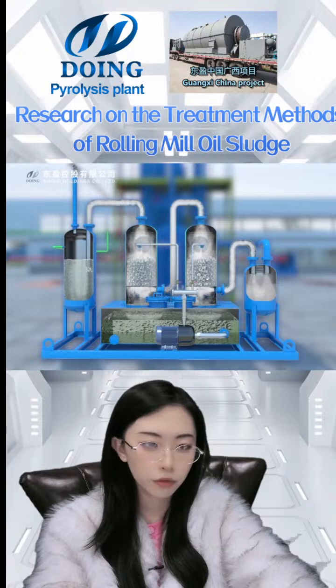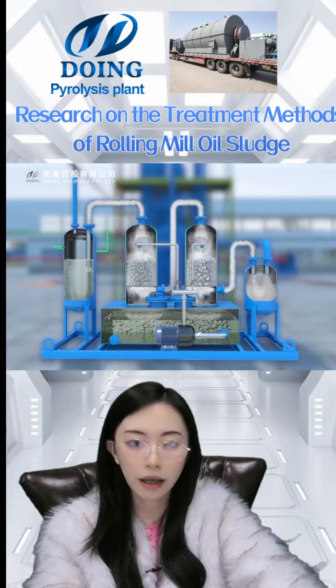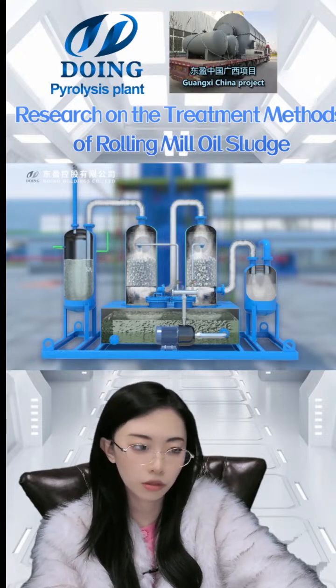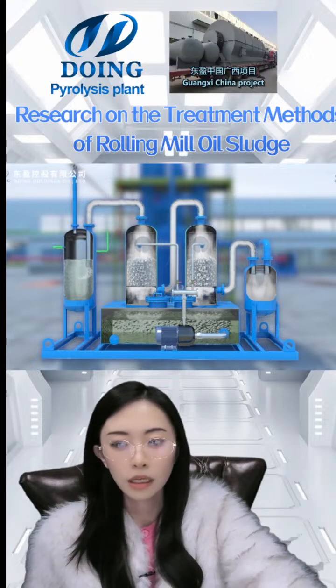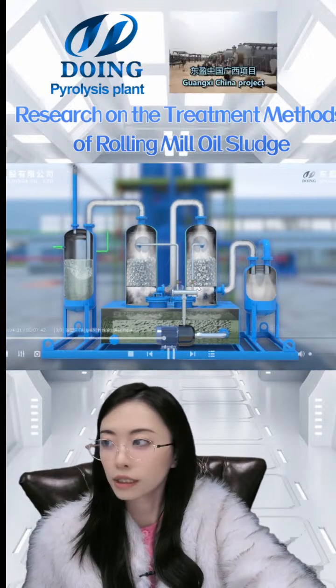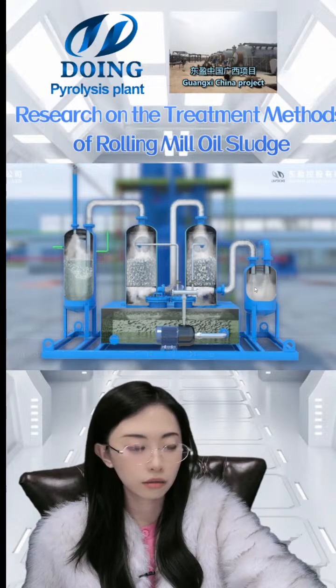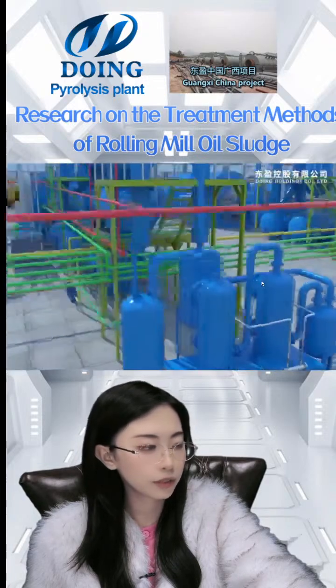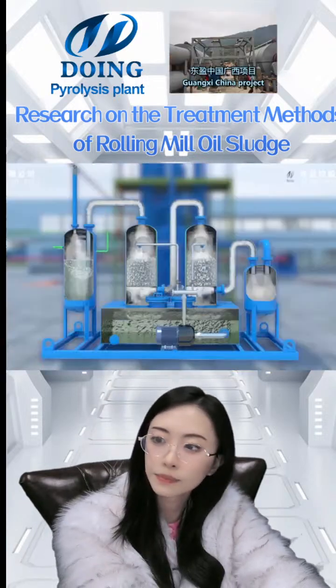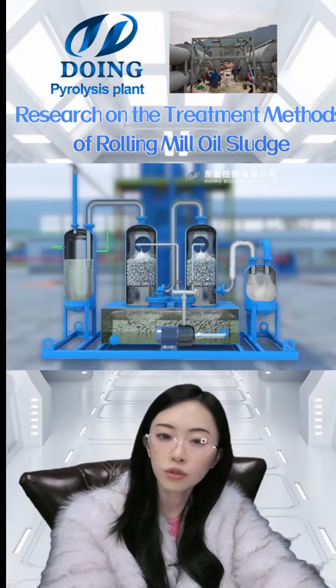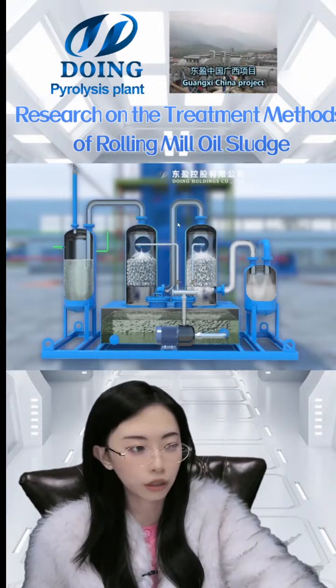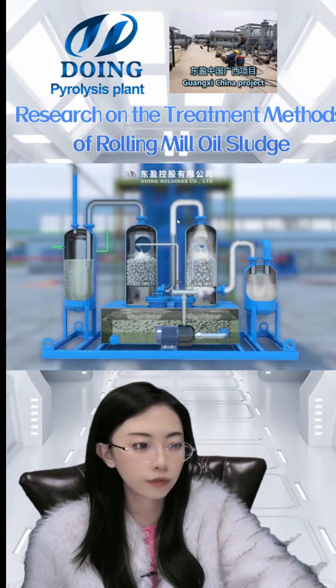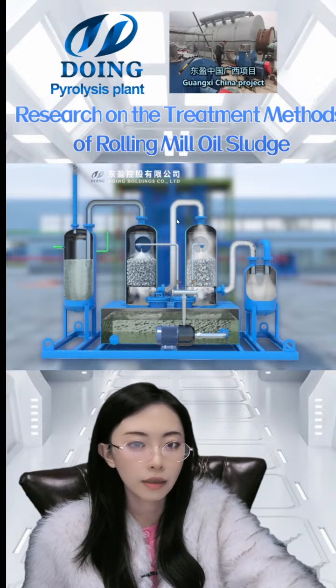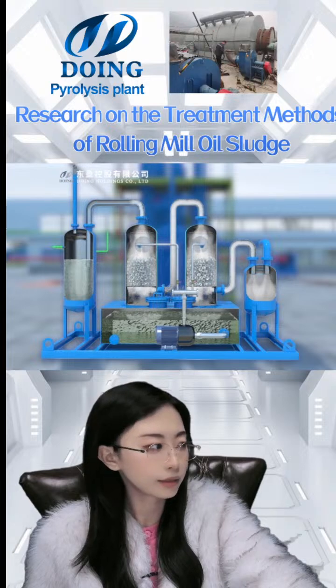This is the odor removal system, our patent device to remove the hydrogen sulfide. The tail gas will first go into this buffer tank to slow down the speed of the tail gas, and then it will go into these two spraying towers to spray, to purify, to remove the hydrogen sulfide by sodium hydroxide.